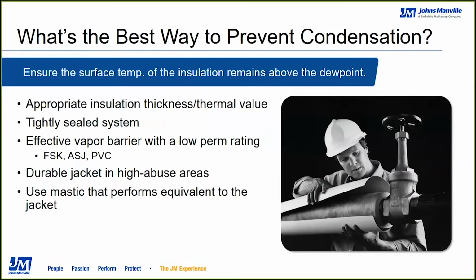So really there are two primary factors that need to be considered as the system is being designed. The first is that you have sufficient insulation thickness to prevent condensation. So while you have a cool pipe in this particular picture, you want to make sure you have enough insulation that you can get the surface temperature of that system above the dew point.